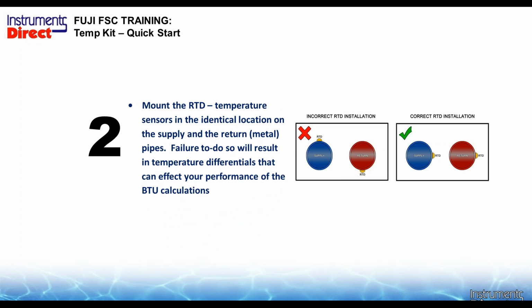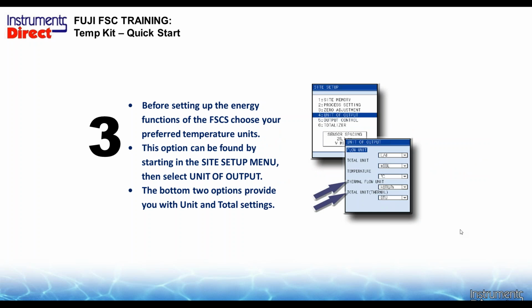So the key here is installation. If you're going to monitor and strap on temperature for BTU monitoring, plus or minus a few degrees basically messes up your information. It's garbage. So what you need to do is have an accurate set of RTDs that are matched pair, and they need to be installed like each other. So if you were to put one at 12 o'clock and one at 6 o'clock, heat rises, you could be a couple of degrees difference between these matched pairs when you start the ball game. And here, if they're both at 3 o'clock, they're both going to be at the same temperature, and you can monitor that performance before you start your test.